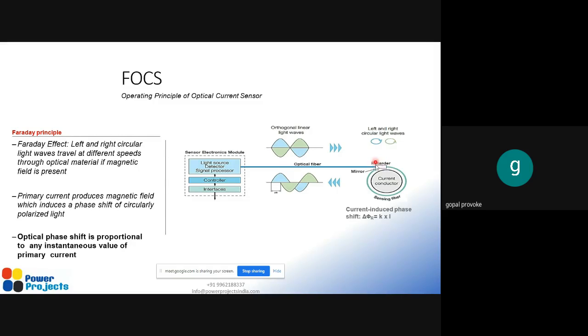In the optical fiber, we convert the signal into light, and the fiber carries this light through a retarder and mirror mechanism, circulating it around the current carrying conductor. Whenever the conductor carries current, flux is present around it, and this flux interacts with the light being carried, creating a phase difference in the light signal. The mirror reflects these changes, and we receive this light back through the fiber optic cable. Based on this phase shift, we can identify the magnitude of the current flowing in the conductor.